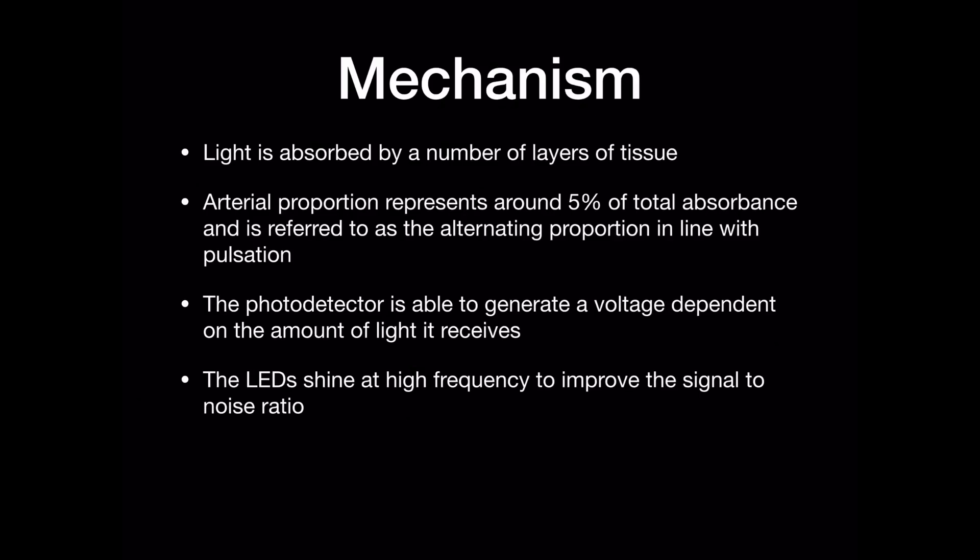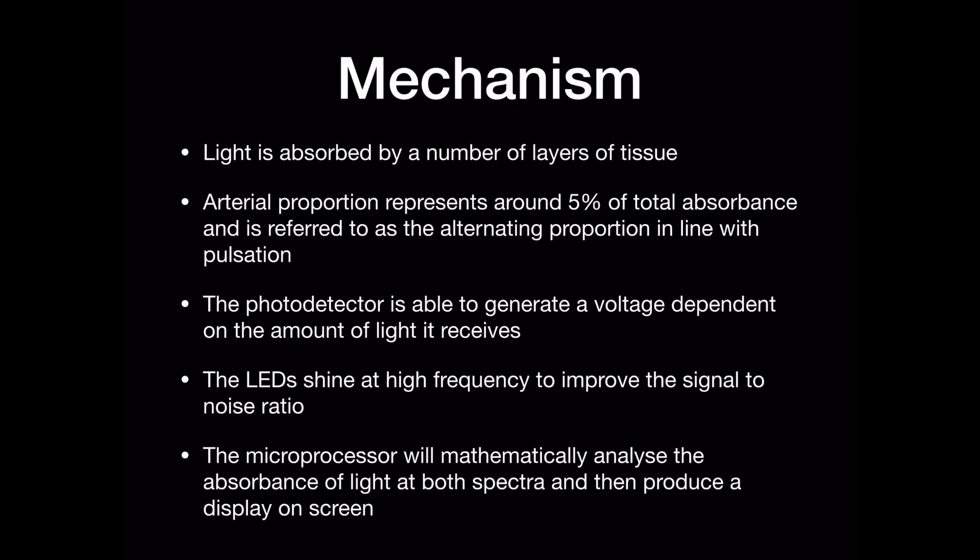The LEDs shine at high frequency to improve the signal to noise ratio and the microprocessor analyses the absorbance of light at both spectra and produces a display on the screen.